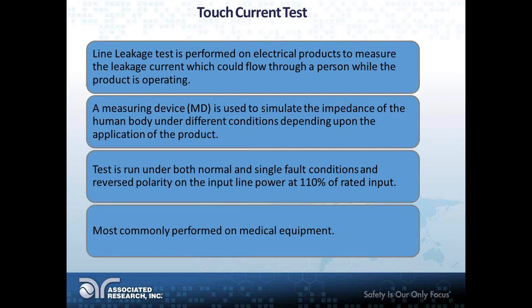Okay, lastly, the last test that we're going to quickly cover is the touch current test, also commonly known as the line leakage test. This test is performed on electrical products to measure the leakage current which could flow through a person while the product is operating.